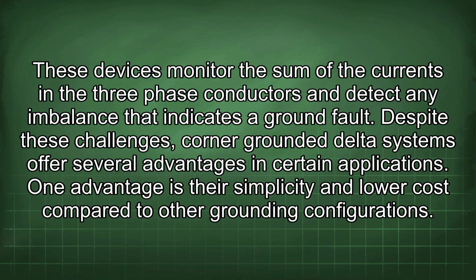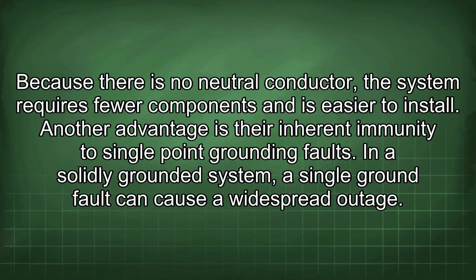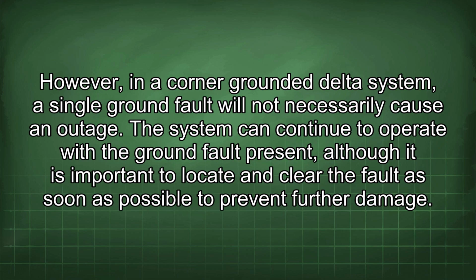One advantage is their simplicity and lower cost compared to other grounding configurations. Because there is no neutral conductor, the system requires fewer components and is easier to install. Another advantage is their inherent immunity to single-point grounding faults. In a solidly grounded system, a single ground fault can cause a widespread outage. However, in a corner-grounded delta system, a single ground fault will not necessarily cause an outage. The system can continue to operate with the ground fault present, although it is important to locate and clear the fault as soon as possible to prevent further damage.